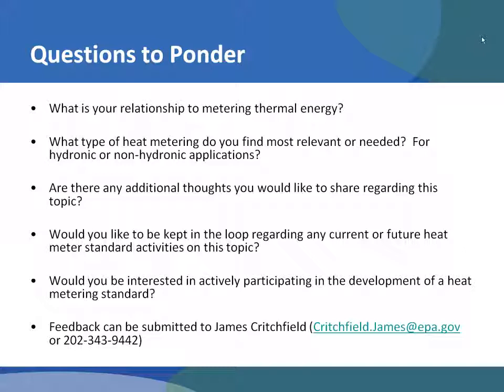I think the most important thing is that we have found that in Massachusetts, when you look at the payback, if you are going to qualify for the APS system and earn credits and you have a reasonably efficient CHP system, as you get larger and larger in size, the paybacks on the metering costs get smaller and smaller, to where you're really typically under 2 months for a payback. Given a 10-year lifetime, you're at about 2% of your lifetime that you've paid back the metering, and from then on it's paying for itself. I mean, it's making money for you.